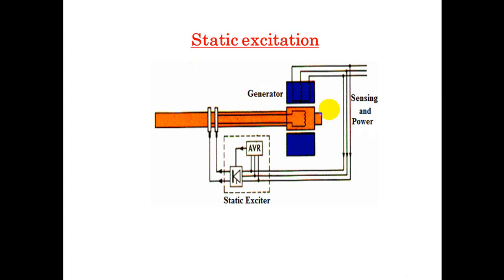Fourth method, brushless excitation without pilot exciter. There are three heavy-duty current transformers arranged in the generator output lines, as shown in the figure. Under short circuit conditions, when the generator output voltage is very low, the current transformers pick up the heavy short circuit current. A necessary requirement is network operation so that protection may operate reliably.